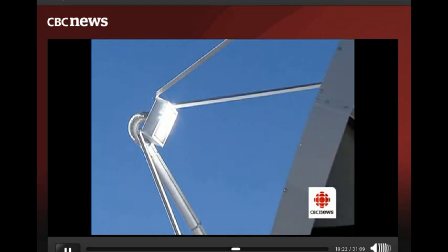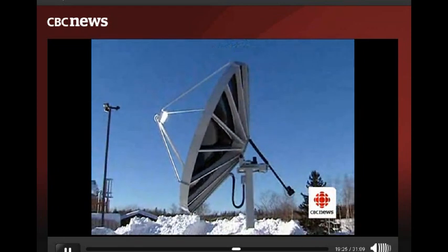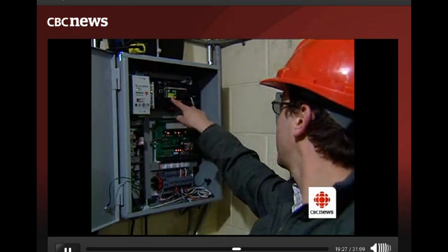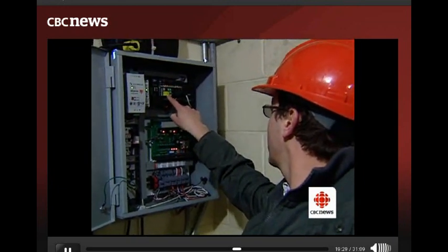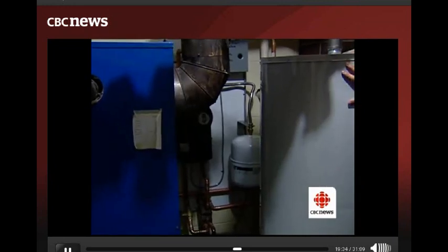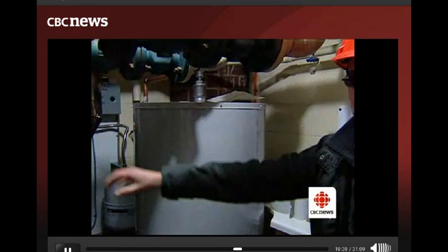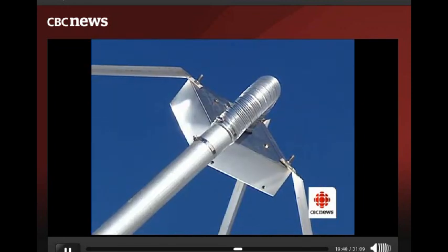At the focal point, in this box, liquid is heated. It then flows through the boiler room in the basement — it's coming into the building right now. We're running at around 78 degrees Celsius. A heat exchanger then preheats the water just before it enters the boiler. The money is saved when less energy is used to heat the water.